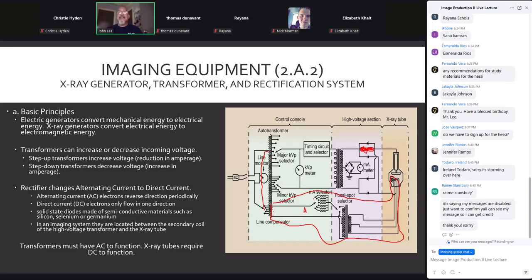We're going to get to our mA selector, which is a rheostat. That device is a variable resistor, and it allows us to change the amount of resistance in the circuit. By changing the resistance, we change the amount of current that is allowed to flow through the filament. The more current we put through the filament, the hotter it gets, the more electrons we have. The lower the current, the lower the temperature, the fewer electrons we have. That's why we use the rheostat to adjust the mA, because ultimately it changes the temperature of the filament, which changes the amount of electrons that we have for our exposure.